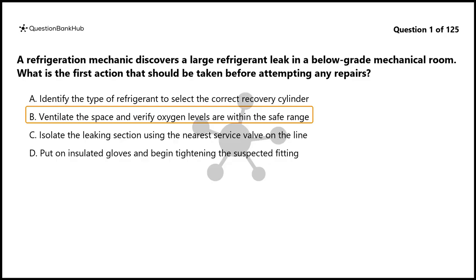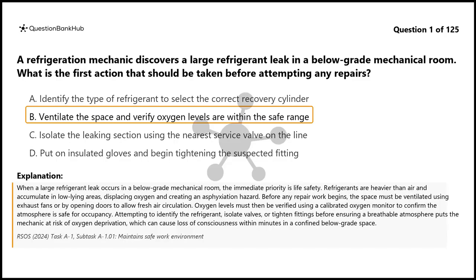The correct answer is B. When a large refrigerant leak occurs in a below-grade mechanical room, the immediate priority is life safety. Refrigerants are heavier than air and accumulate in low-lying areas, displacing oxygen and creating an asphyxiation hazard. Before any repair work begins, the space must be ventilated using exhaust fans or by opening doors to allow fresh air circulation. Oxygen levels must then be verified using a calibrated oxygen monitor to confirm the atmosphere is safe for occupancy. Attempting to identify the refrigerant, isolate valves, or tighten fittings before ensuring a breathable atmosphere puts the mechanic at risk of oxygen deprivation, which can cause loss of consciousness within minutes in a confined below-grade space.